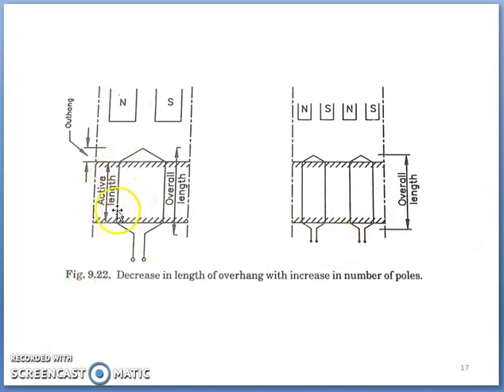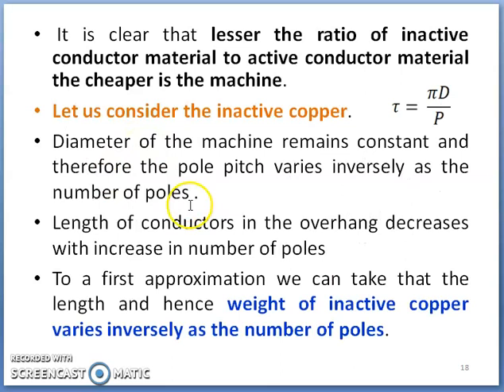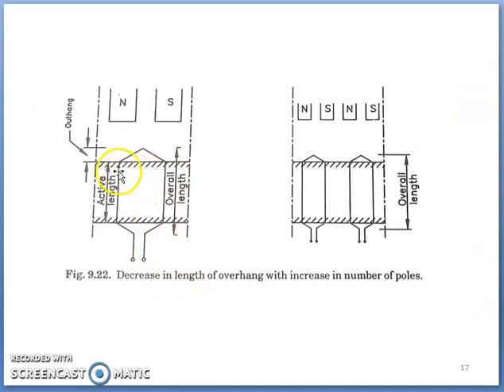The conductor which is exactly placed in the slot and which takes active part in energy conversion is active copper. The copper used in the overhang, just to make the connection between two conductors beyond the active length, is called inactive copper. This ratio of inactive conductor material to active conductor material will decide the cost of the machine, and depending upon the number of poles used in the design, this overhang and inactive copper material requirement will change.